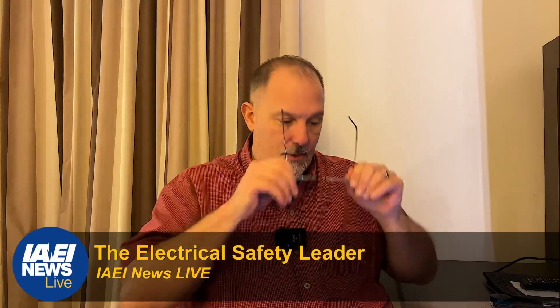So when they came out with the tamper-resistant receptacle, they realized we have to do more tests on it. So they did. They have additional performance requirements for receptacles, specifically for tamper-resistant receptacles. They have to apply a probe test. Now you think about it. You want to keep someone's fingers out. You want to keep objects out. Well, you need a probe test.